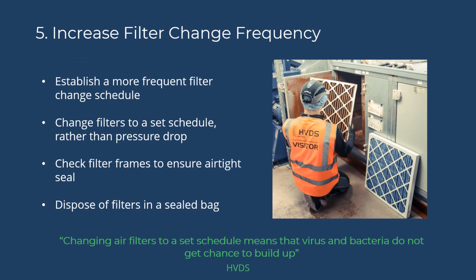Regular filter changes will help to combat microbial growth on filters, and of course, as indicated by REHVA, clogged air filters reduce supply airflow, which has a negative effect on indoor contaminations. So maintaining a regular filter change schedule and increasing frequency according to the findings of your ventilation strategy review is important. HVDS would recommend changing filters to a set schedule rather than to pressure drop readings. This is a more preventative course of action and eliminates the risk of overlooking this crucial element of maintaining an air handling system.